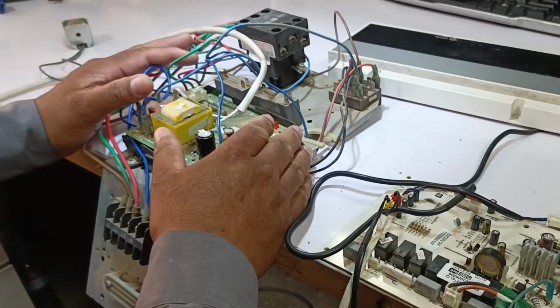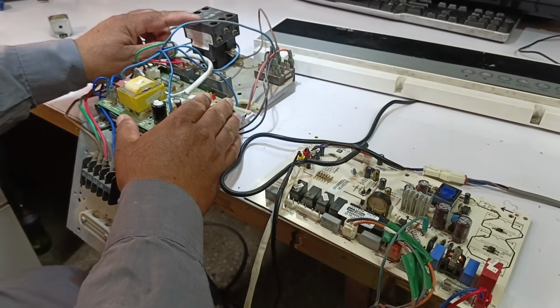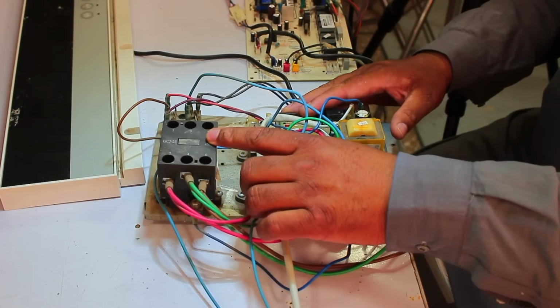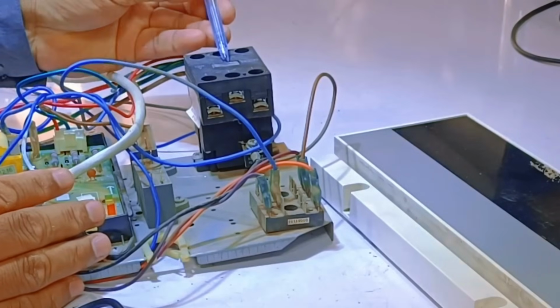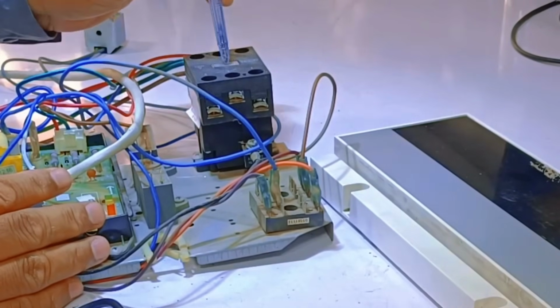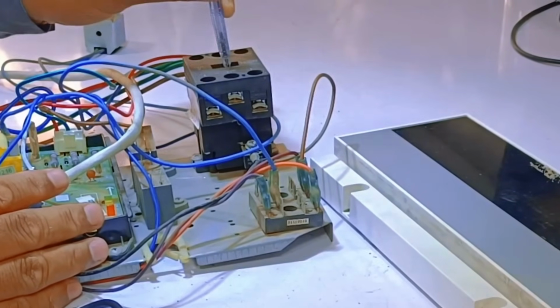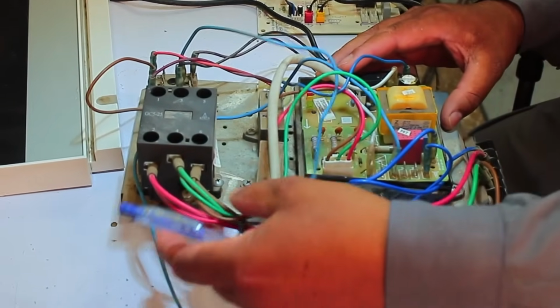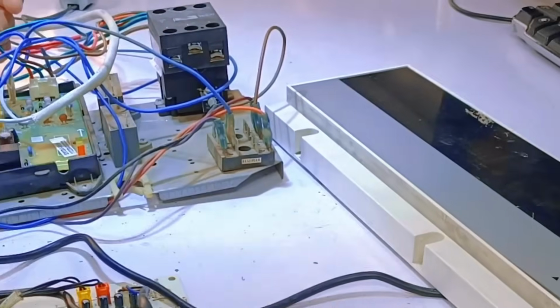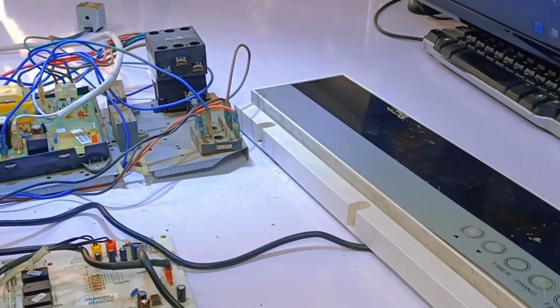When I removed this circuit board from the unit, I noticed that this connector here was not engaging properly. Let me explain to you what normally happens. I'll press this connector and show you. When you press it, it engages like this. When it engages, the three-phase supply passes through to this side, and as a result, the compressor starts running. This outdoor circuit board operates with a three-phase supply.